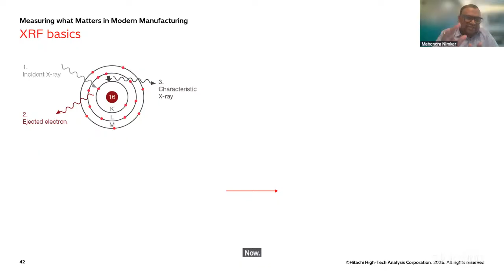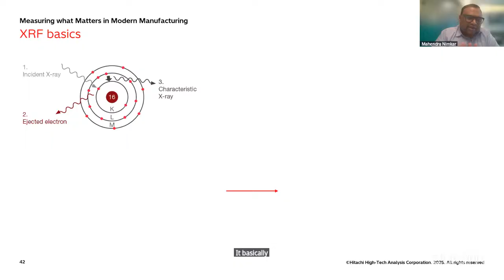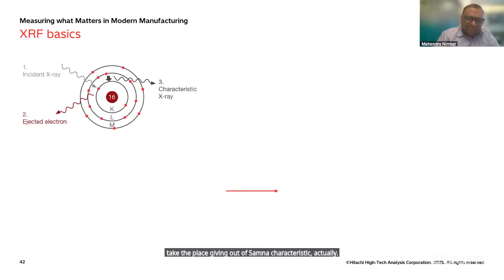So basically, what we are doing here is typically what happens in XRF. Your incident X-ray, or primary X-ray, falls on the sample. It ejects some of the electrons, and the secondary outer shell electron tries to take the place, giving out some characteristic X-ray, which we call the fluorescence. So we get this kind of graph, intensity versus keV or electron volt. The electron volt is basically the energy required to push the electron out of the shell, and whatever counts you get is basically the intensity for the element which is present.